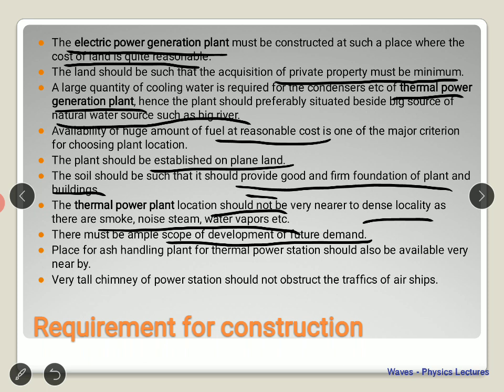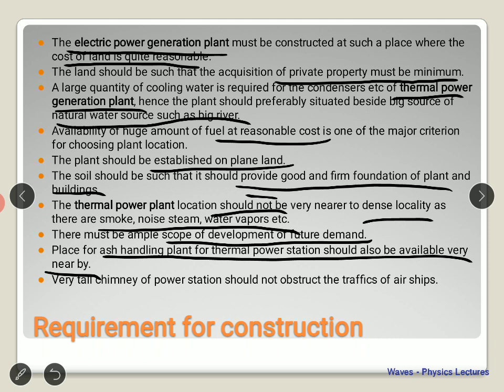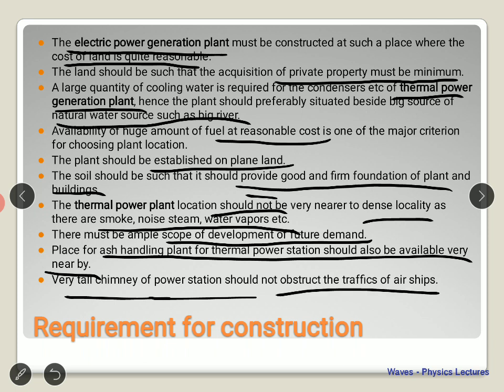A place for the ash handling plant should be available nearby, since coal generates a lot of ash that needs proper disposal. The plant should not be near a dense locality because it generates smoke, noise, steam, and water vapors. The tall chimney should not obstruct air traffic, so it should be far from the city to avoid disrupting normal life. In the next class we will look at the advantages and disadvantages of thermal power plants.